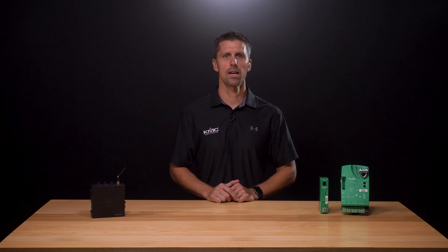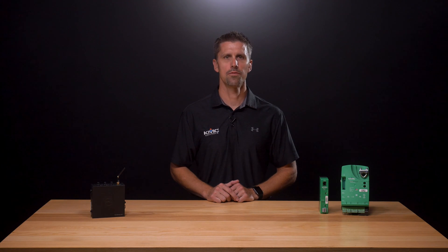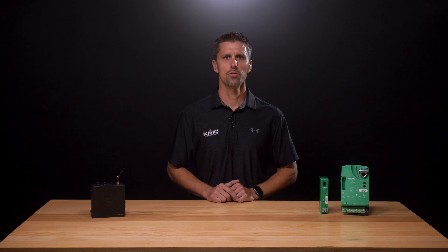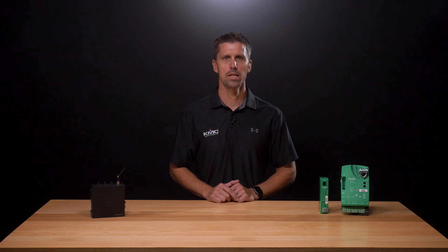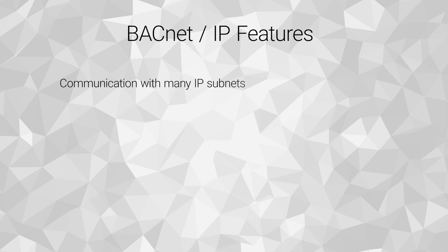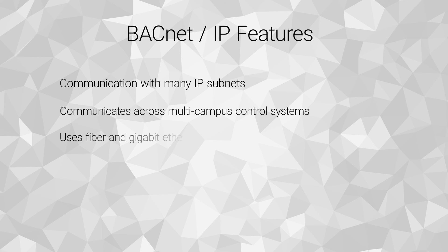BACnet supports seven types of networks and physical media to connect devices. The two most prevalent in use today are BACnet over IP and BACnet over MSTP. The IP in BACnet over IP stands for Internet Protocol, one of the main protocols that allow computers to talk with each other over a network. BACnet over IP allows for communication between different IP subnets, multi-campus control systems, and can even use fiber and gigabit Ethernet communications.